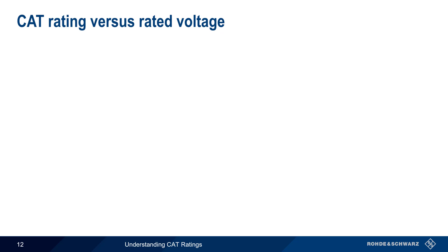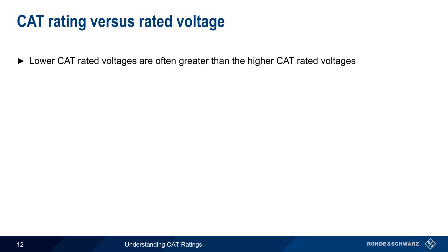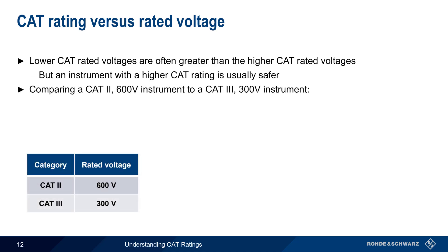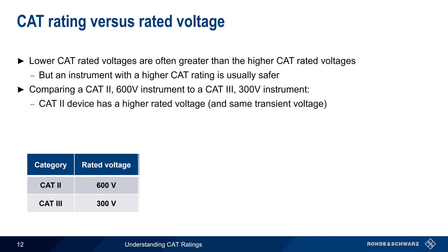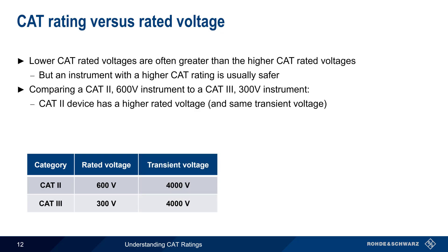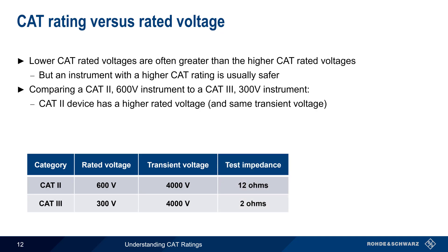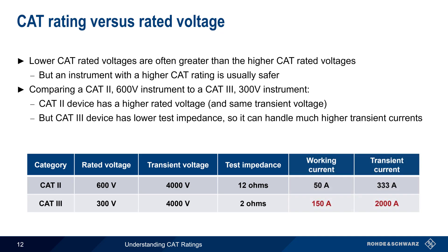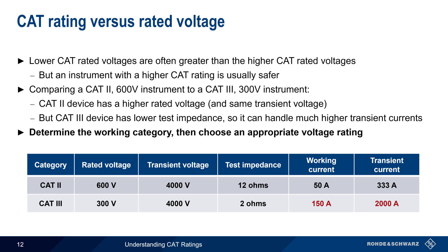When instruments have multiple CAT ratings, the lower CAT rating often has a higher rated voltage, but instruments with a higher CAT rating are usually safer. Let's compare a CAT 2 600 volt rated instrument with a CAT 3 300 volt rated instrument. The CAT 2 device has a higher rated voltage and can safely withstand the same transient voltage as the CAT 3 device. But note that the test impedance is different for these two categories. The lower test impedance of the CAT 3 device — 2 ohms versus 12 ohms — means that they can handle both a higher working current and a much higher transient or peak current. The best rule of thumb, therefore, is to first determine the category in which you are working, and then choose an instrument with an appropriate voltage rating from that category. This provides the greatest safety for both the instrument and the operator.